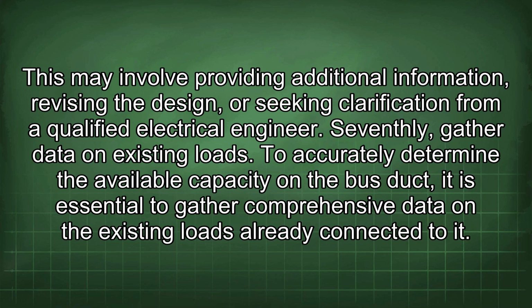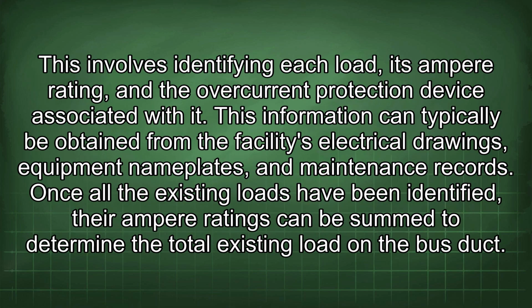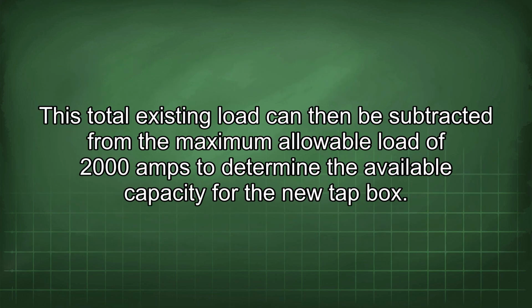Seventhly, gather data on existing loads. To accurately determine the available capacity on the bus duct, it is essential to gather comprehensive data on the existing loads already connected to it. This involves identifying each load, its ampere rating, and the overcurrent protection device associated with it. This information can typically be obtained from the facility's electrical drawings, equipment nameplates, and maintenance records. Once all the existing loads have been identified, their ampere ratings can be summed to determine the total existing load in the bus duct. This total existing load can then be subtracted from the maximum allowable load of 2000 amps to determine the available capacity for the new tap box.